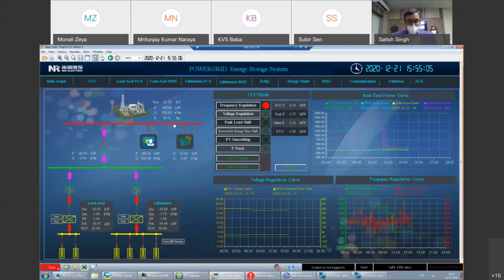So if your frequency goes beyond the third band, so these values can be discussed. We have just been parameterizing these values, doing testing and all those things. So these values we are trying to capture based on the historical data and other things, so that's fine. Now, if my frequency goes beyond the last threshold point, say 49.5 or 50.5, the battery discharge rate is full, to the full, maybe 100% extent.